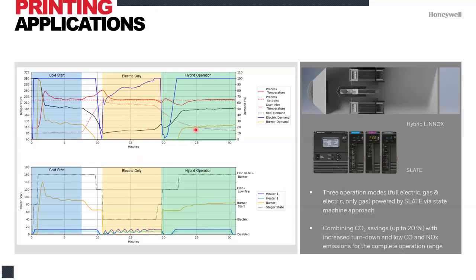As a second part of the simulation, we assumed a different product running through, with a higher heat demand. So the preheat temperature drops because the product absorbs more heat, and we see an increase as the burner is enabled again.